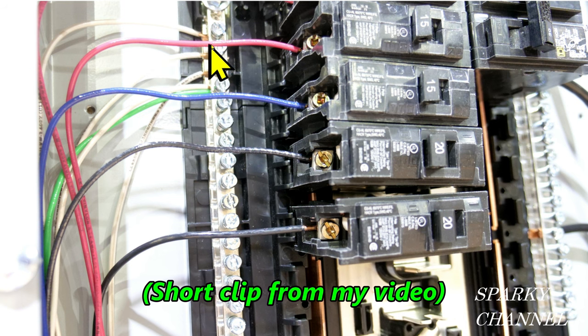Now this 14 gauge hot wire goes to this circuit breaker, which is a 15 amp circuit breaker. So that's correct. And it's nicely installed, not too much copper showing. This blue 14 gauge hot wire is going to a 15 amp breaker. It's nicely installed. That's excellent.